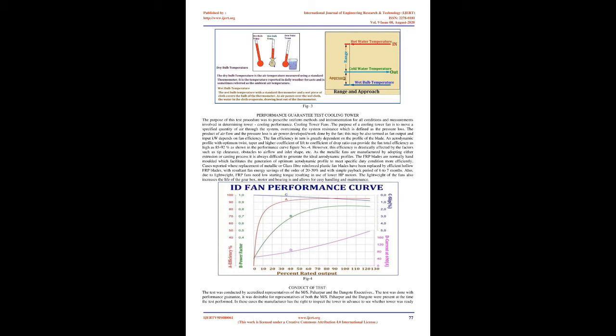The factors to be considered in sizing a cooling tower are the heat load, approach temperature, and wet bulb temperature. The heat load is determined by the process duty. The local climate determines the wet bulb temperature, and the remaining factor, approach temperature, is determined by how low the water has to be. The driving force for heat transfer is the difference in enthalpy between the air contacting the water surface and the bulk air stream. The enthalpy content of moist air is the summation of the sensible heat content of both the water and air present, the latent heat of the water vapor, plus, for non-saturated mixtures, the superheat of the water vapor.